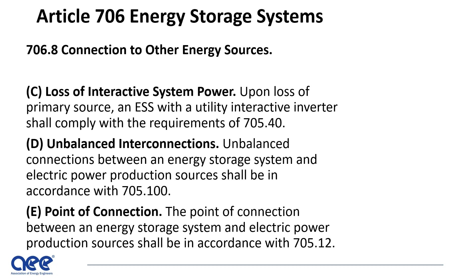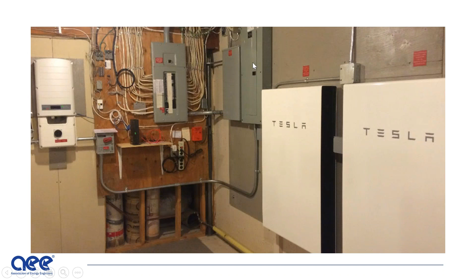The other things that you run into are requirements for locations, right? You need to make sure that wherever you are, you have proper ventilation, proper guarding of any type of live parts, so that if somebody opens a door, they're not immediately exposed to live parts, and proper spaces around those components. One of the reasons spaces matter is that electricity, if you don't have enough space, will jump. If you have a voltage that might require 1-inch spacings, and you only have a 1/2-inch spacing, you could potentially have a fault occur, and that's why the spacings become important. Again, this is more showing an installation in a commercial building where you might have connection into your power distribution system.